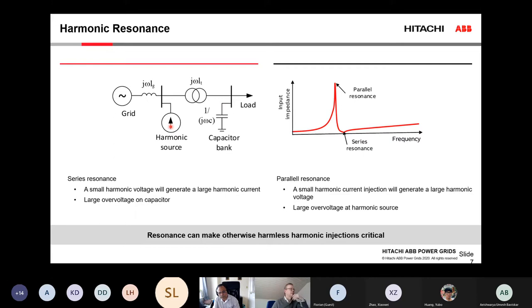And if we inject harmonics exactly at that parallel resonance frequency, even a small harmonic injection will give us a huge harmonic distortion in the voltage.